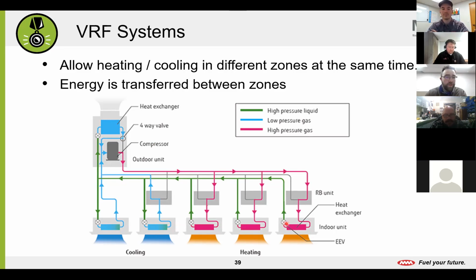The 2 on the left are in cooling. The 3 on the right are in heating. And that's going to be controlled by an individual thermostat for each zone. And VRV lets us have that individual control. So if we have, say, our zone 3, our middle guy here, we reach our set point, we're nice and warm, and then we decide we want to cool that space, we can easily kick that space on into cooling. It will switch into cooling and start cooling the space without interrupting any of the other zones.